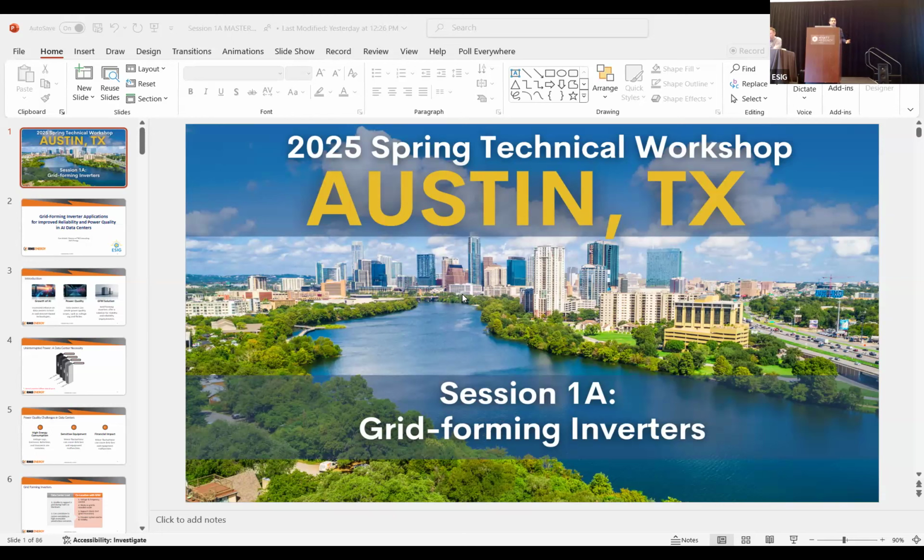We had one project where we were almost considering installing a GFM. The short circuit ratio was 2.2, but we tested the battery and worked with the OEM, and they were able to provide a stable response using the GFL at the POI for 1.8. So we could do GFM. We were more than willing to go for GFM, but we are not enabling GFM just for the sake of enabling GFM. We are more pragmatic in our approach.